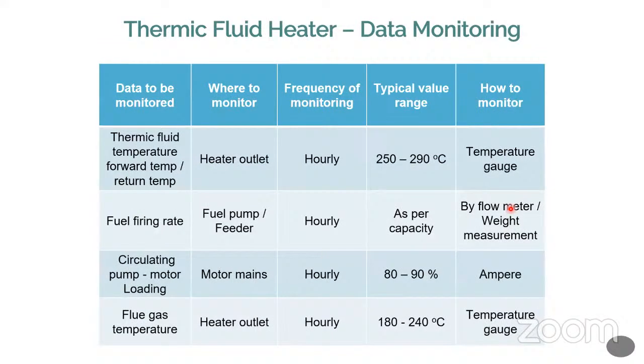Now, what are the data to be monitored if you have a TFH? Similar to your boiler, the same thing is applicable for your boiler as well as your TFH. Okay. Now, what are the important parameters I have to monitor, what is the frequency of monitoring, and what is the range of values? The range of values depends on the site condition, location, all those things. So I'm not mentioning very clear-cut typical values of the ranges. Rather, all 4 parameters, like data to be monitored, where to be monitored, and how to be monitored, are very important. Similarly, the frequency of monitoring also depends on the site condition and the layout of the design.